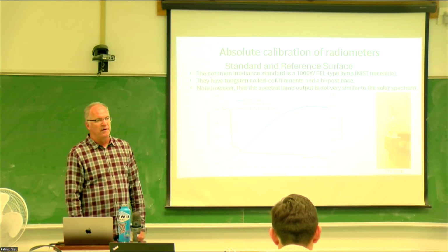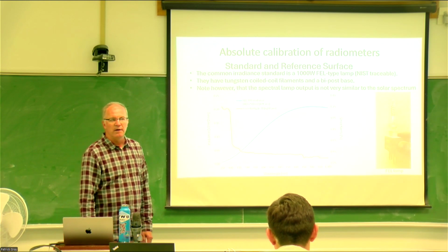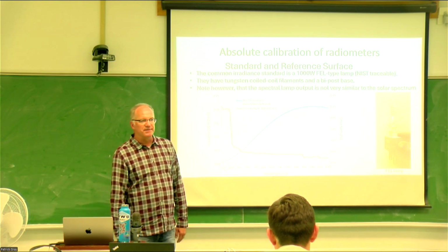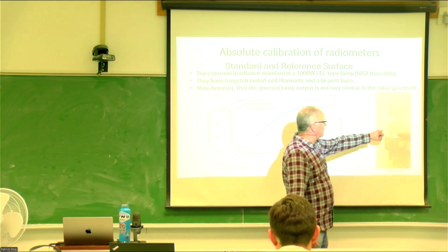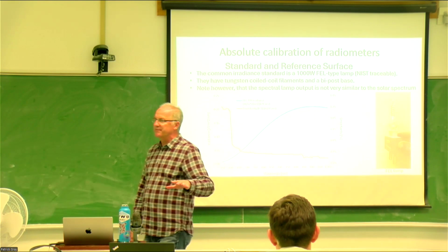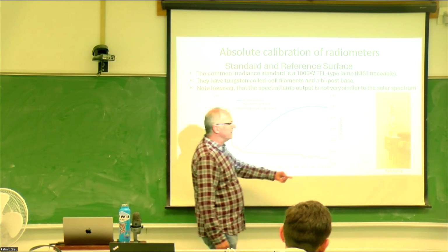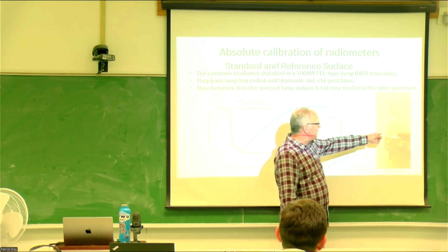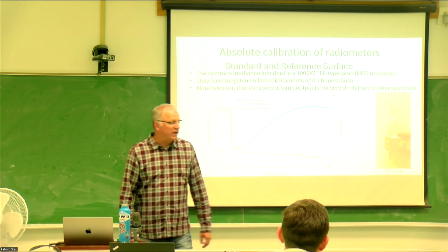By the lamp, is this something we would see in a handheld? No. This is the only place you'd really ever see this, in a radiometric calibration, which I'm about to show you. Basically, there are constraints. These things can only be turned on for 40 hours before they go out of spec, meaning you can't use it for calibration anymore. They're highly sensitive, even more so than the ACS. Don't put your thumb on an ACS window. And if you touch one of these, you have to throw the whole thing away. So 40 hours? 40 hours of burn time, yeah.